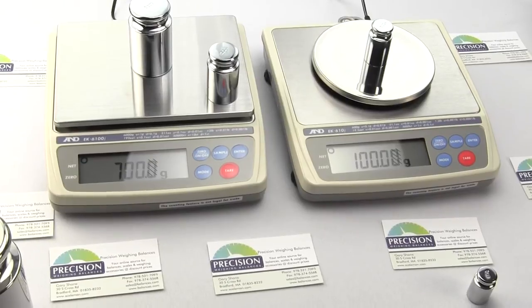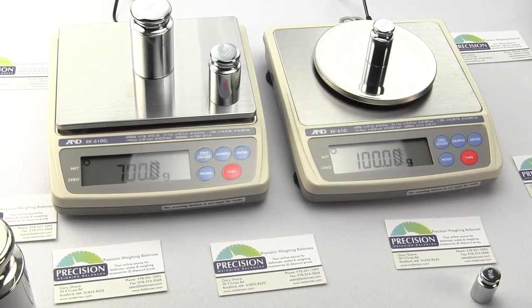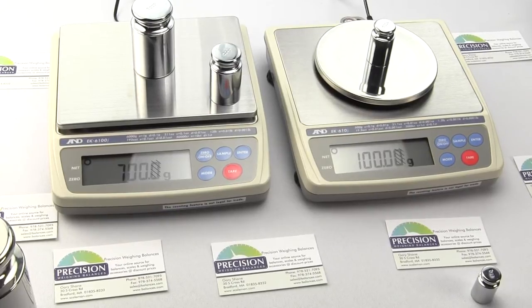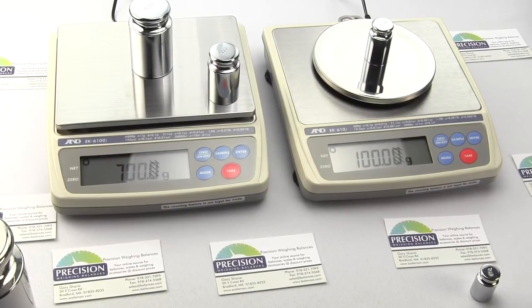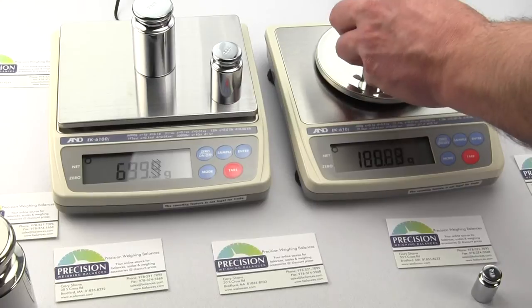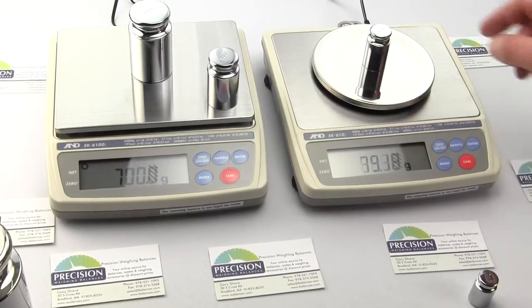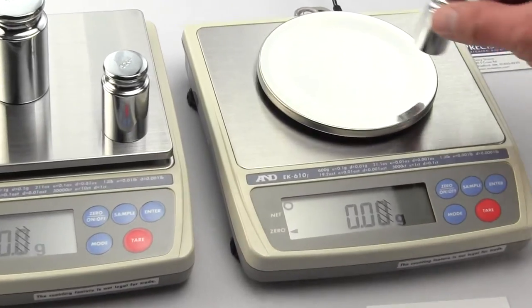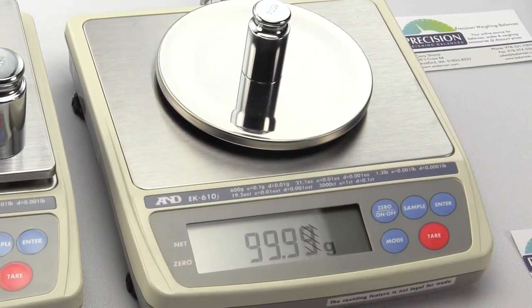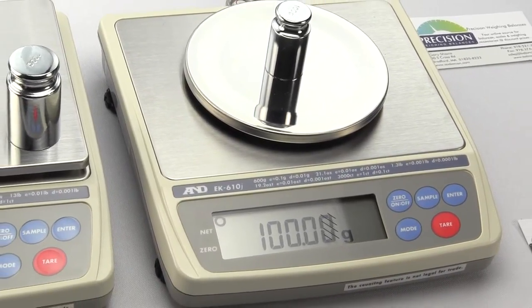Although the EK6100i increments in tenths of a gram, it's only legal for trade to one gram. The National Conference of Weights and Measures issues the NTEP certificate of conformance upon successful completion of the evaluation process. Part of this testing requires placing a calibration weight at approximately 50 percent of capacity on the platform one hundred thousand times. So only high-quality, well-engineered scales with the highest quality load cells can be approved for legal for trade.